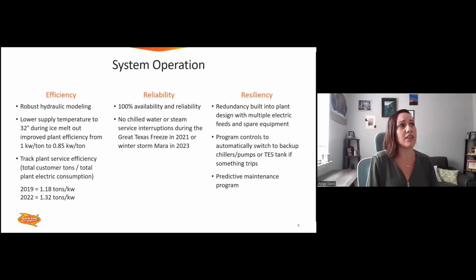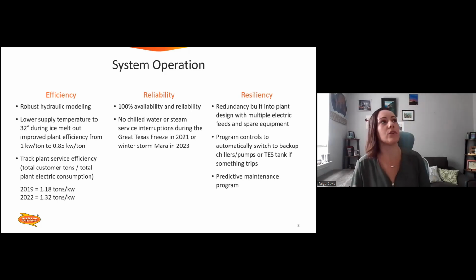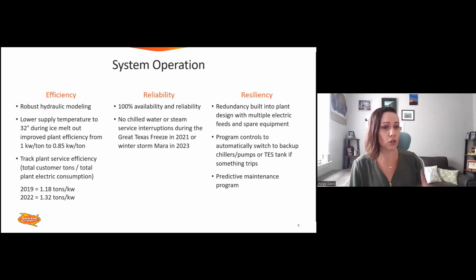We do a lot of things to make sure our plants run efficiently. We have hydraulic modeling, which we are constantly updating, and we use that when we're looking at how we're going to expand our system, how we're going to add customers, and what we need to do to adjust our system to make sure that everything is running as best it can. We've made various improvements in the plants over the years in our operations. So with our thermal energy storage tank, whenever we're melting that ice tank out, we're able to lower our supply temperature in the system to 32 degrees. And that has improved our plant efficiency from 1 kilowatt per ton to 0.8 kilowatts per ton.